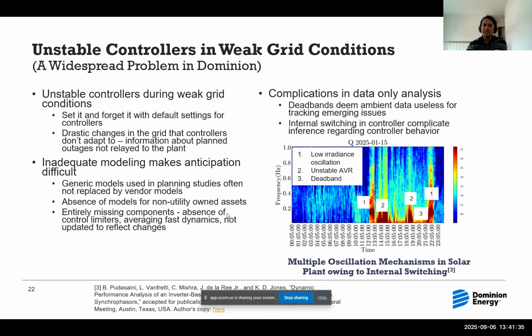Unstable controllers during weak grid conditions are so common in our system, and the reason is that in practice there's a set it and forget it mentality around controllers. When a facility interconnects to our system, there's no rigorous testing, like we don't test it against a range of operating conditions. Now imagine having devices like that in the system, and then you take some outages, and the oscillations or instabilities reveal themselves. That's happening very commonly in our solar plants.